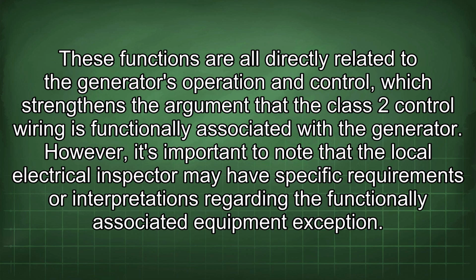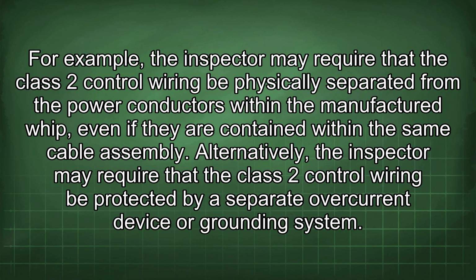However, it's important to note that the local electrical inspector may have specific requirements or interpretations regarding the functionally associated equipment exception. For example, the inspector may require that the Class 2 control wiring be physically separated from the power conductors within the manufactured whip, even if they are contained within the same cable assembly. Alternatively, the inspector may require that the Class 2 control wiring be protected by a separate overcurrent device or grounding system.